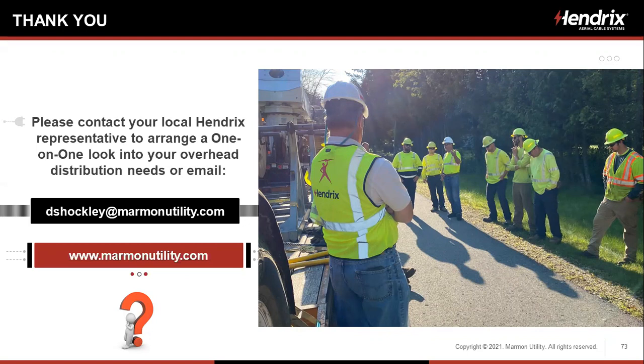I've been called out personally on forest fires with covered conductor down at Smoky Mountain National Park in Tennessee. We had a forest fire past spacer cable because they run it up the ridges to their fire and their antenna farms. The utility called and said, hey, we had a forest fire, come take a look at the cable. The forest fire must have been moving. It was good for a couple of days. Rain put out that forest fire.